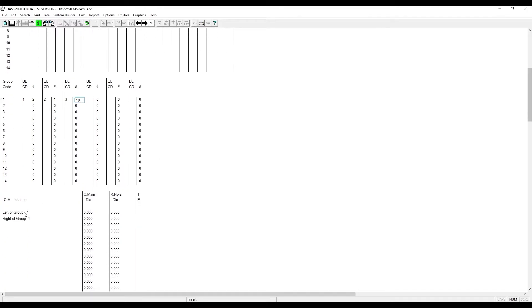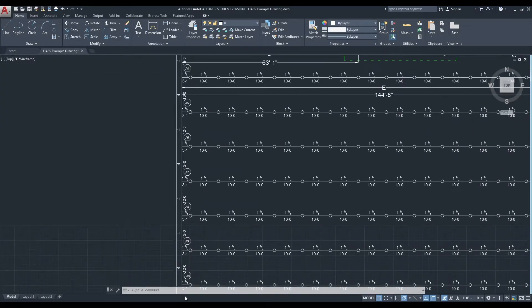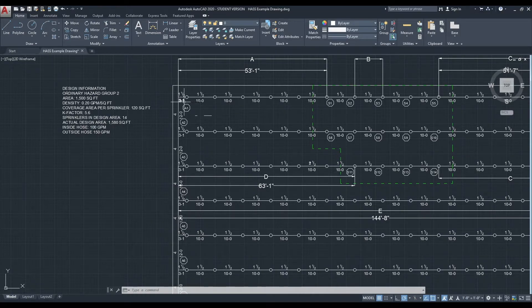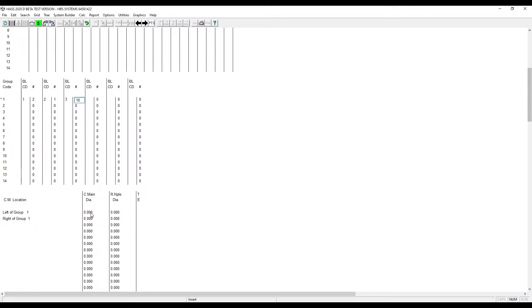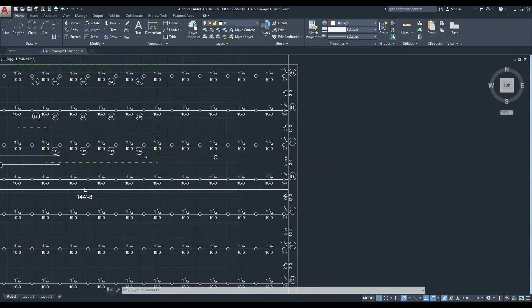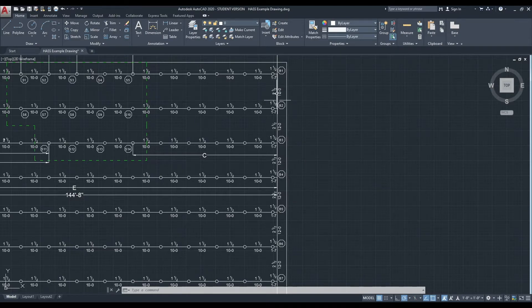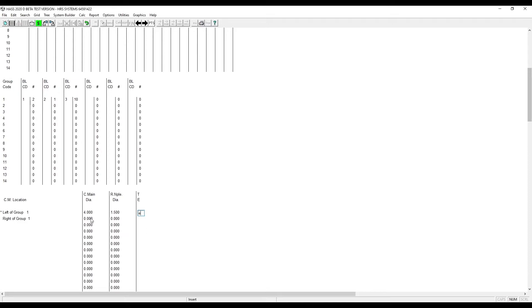Now we need to come in and enter our cross main information as well as our riser nipple. Our cross main on the left side is 4 inch diameter. We'll keep our riser nipple the size of the branch line, which is inch and a half. And then we enter the elbow for the top of the riser nipple. Now we need to do the right side — that's 2 and a half inch pipe. Again we'll keep the riser nipple at inch and a half and an elbow for the top of the riser nipple.